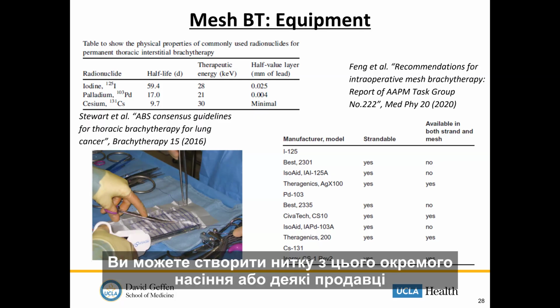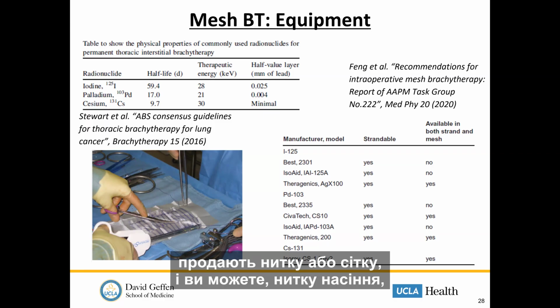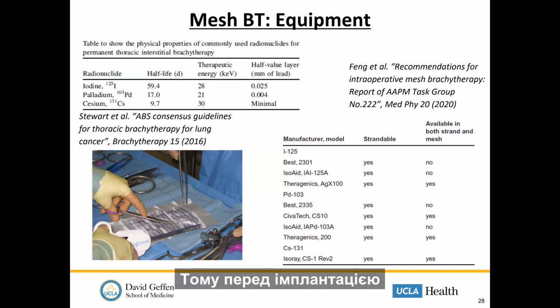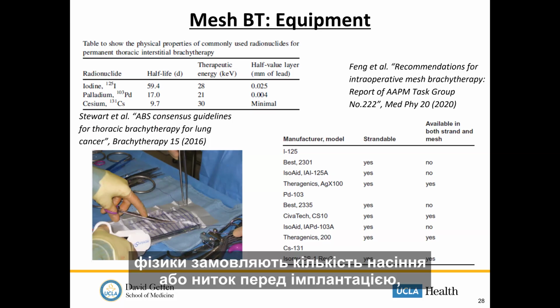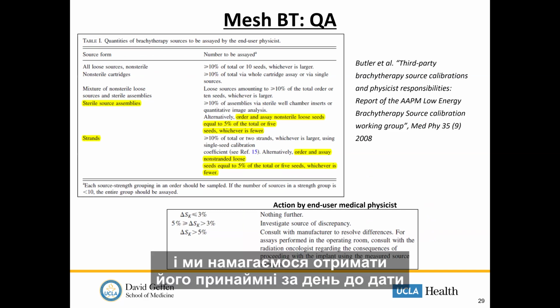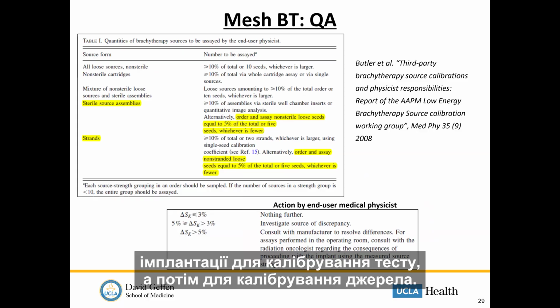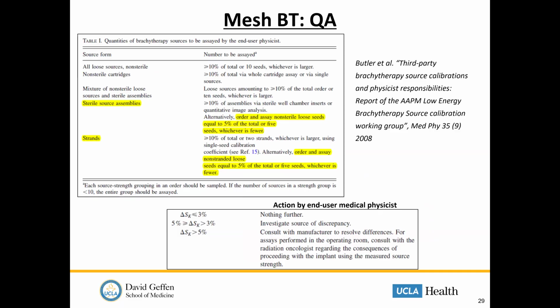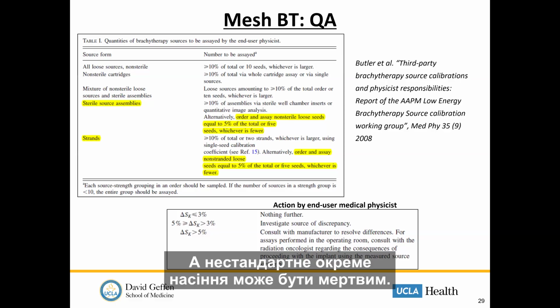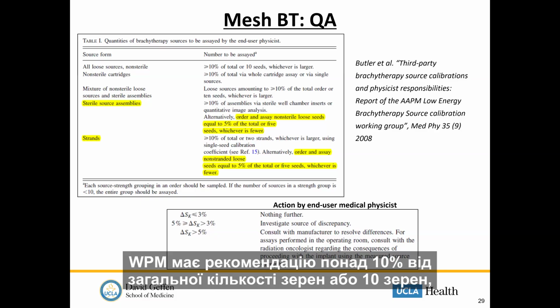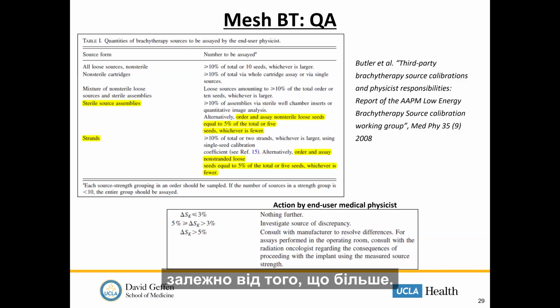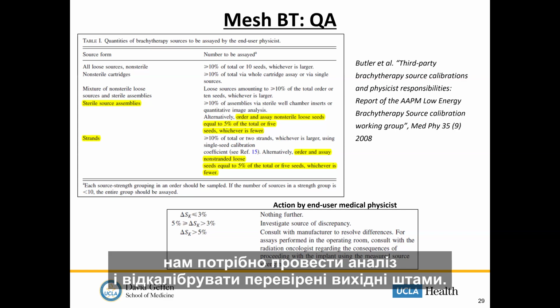You can create the strand seed with these individual seeds, or some vendors sell the strand or mesh type, and from the strand seed you can create the mesh type applicator in the OR. Before the implantation, physicists order the number of seeds or strands, and we try to receive them at least 1 day before the implant date for the assay and source calibration. The AAPM has a recommendation: over 10% of the total number of seeds, or 10 seeds, whichever is larger, we need to assay and calibrate to verify the source strengths.